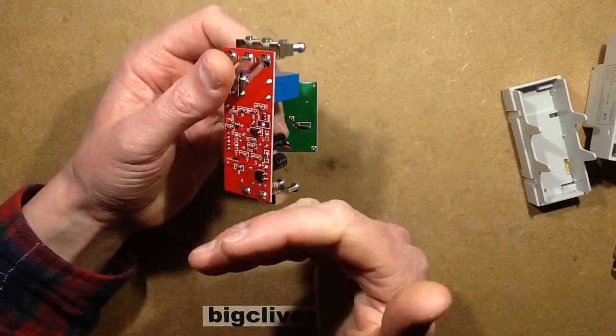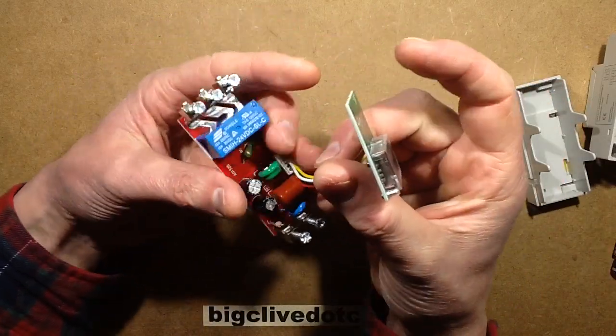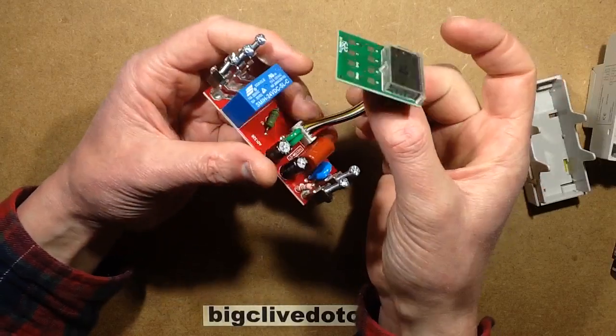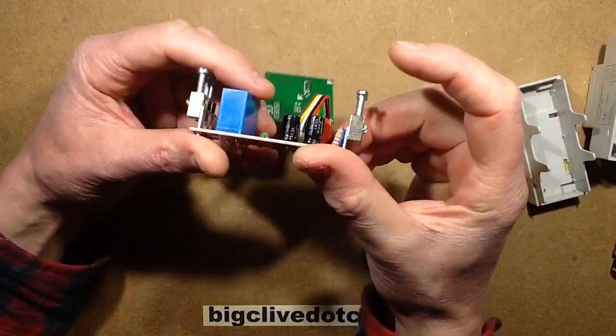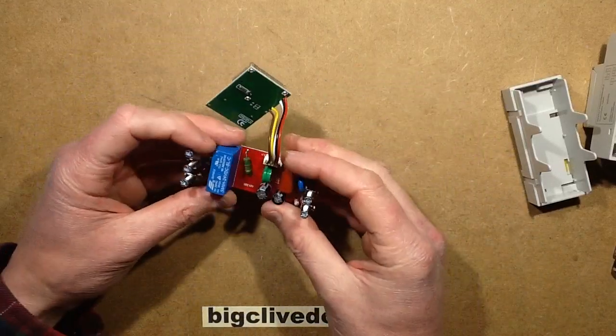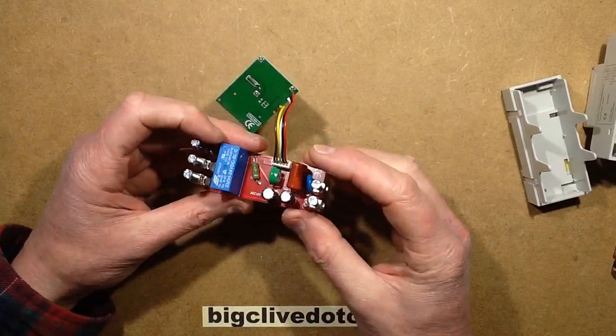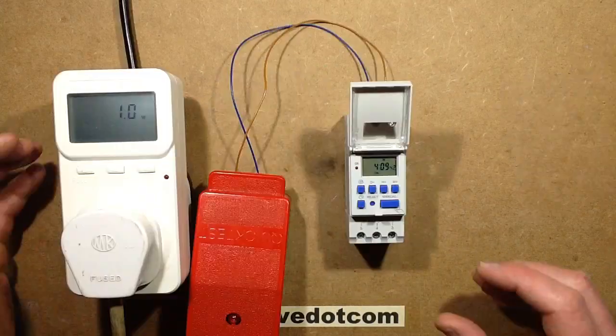I wonder how resilient it is to inductive transients. In the past I've used plug-in time switches to bring in contactors and the digital time switches sometimes crashed when the contactors came in. In another case it was being used to control metal halide discharge lamps, and I'm guessing it was the inrush surge to the power factor correction capacitor that made the contacts weld. I wonder how resilient this is. It's a better quality relay, and certainly that filtration should provide some filtering and separation to keep mains transients away from the circuitry. On the whole it's pretty good, I think that's quite well built inside.